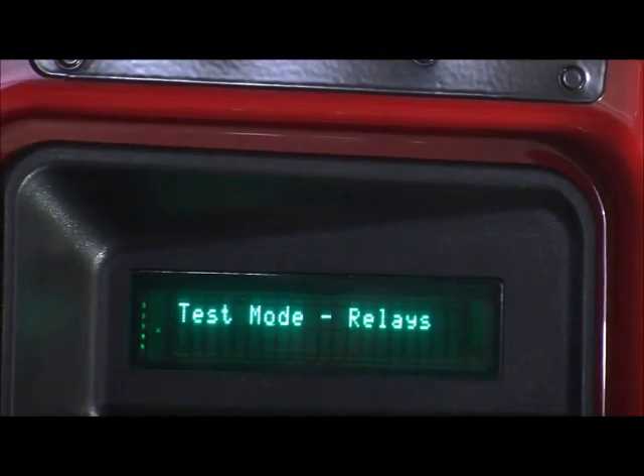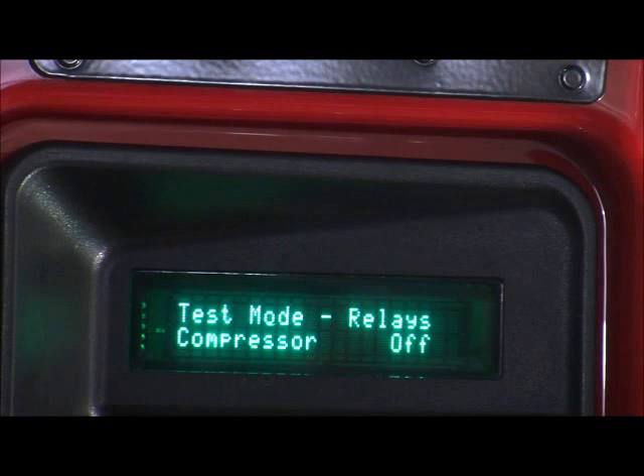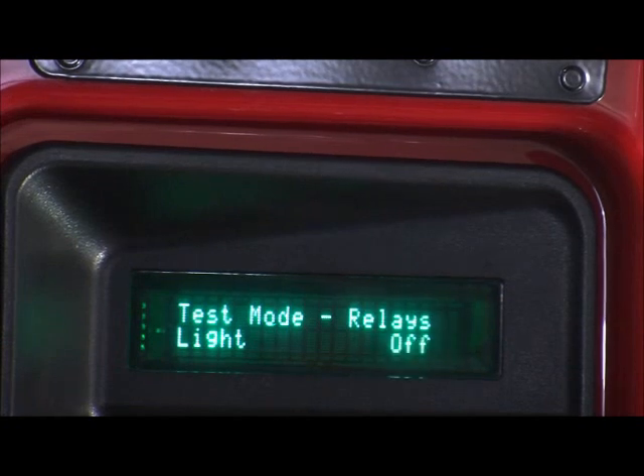Under test mode relays, we can enter in. It allows us to check the relays for the compressor, for the light, for the fan, and for the heater. Heaters will be used in the northern part of the United States and in Canada. If I move to light, for example, and enter with button 4 and change it to on, we'll hear the relay click in the bottom and the light will come on. If I enter on and turn it off, we're back out. We can do the same thing for the fan, for the heater if we have one, and for the compressor.